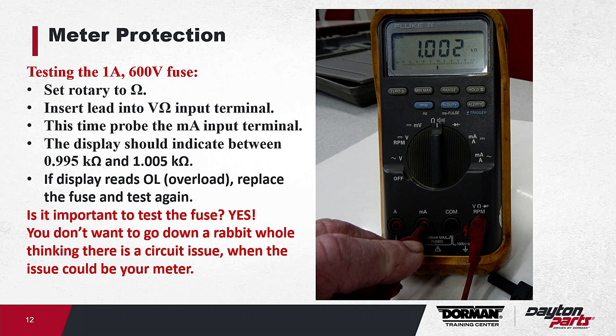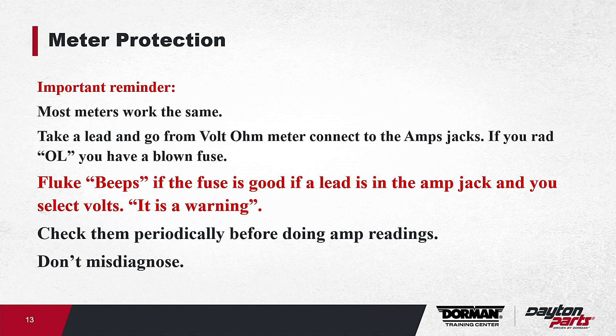So again, important reminder, and most meters work the same way. Take a lead and go from volt ohm meter, connect to an amps jack. If you read OL, you got a blown fuse. Fluke actually beeps if the fuse is good. If a lead is in the amp jack and you select volts, it's a warning. So that's a nice thing. Again, do check them periodically before doing amp readings. Don't misdiagnose.